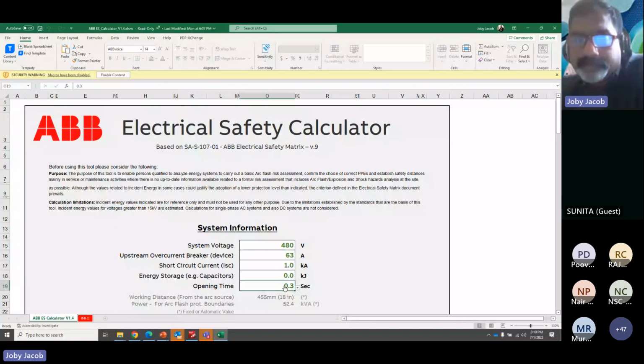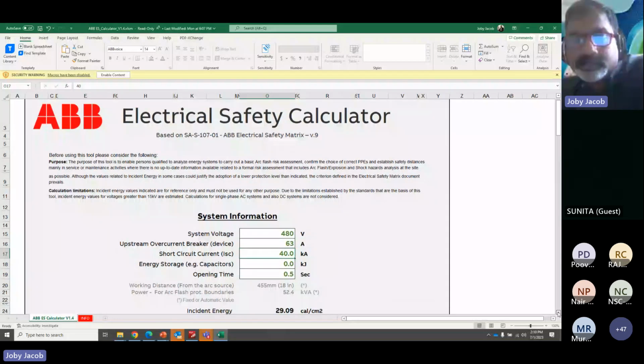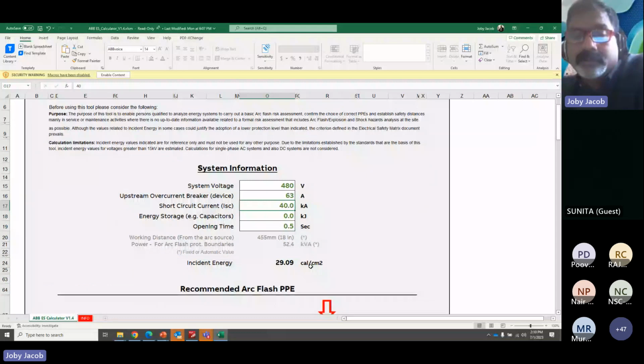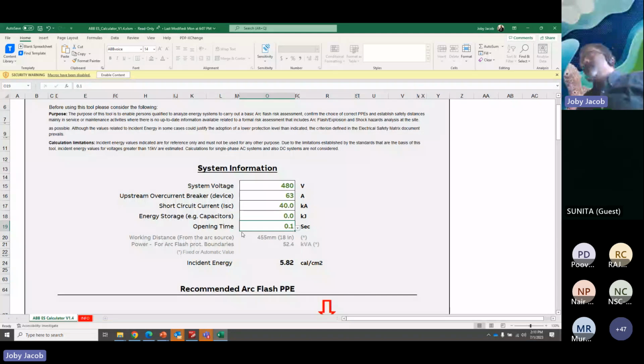if you keep the opening time in this 480 volt itself at 0.5, and let's say the short circuit current around 40 kiloamps or something like that, you get probably an incident energy around 29 calories per centimeter square. For example, if you keep this opening time around, let's say, 0.3, straight away the incident energy reduces to 17.6 calories per centimeter square. And if you keep the opening time to, let's say, 0.2, it's 11. And if it's less than 10 milliseconds, the incident energy is considerably reduced. So if you do an arc flash study in your own premises, this is one of the ways you can reduce or mitigate your arc flash energies, right?